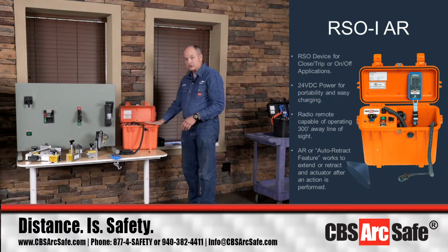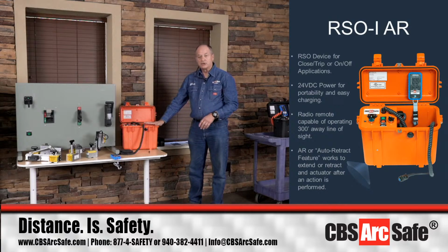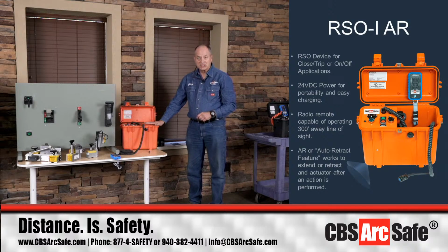It has a smart cycle charger in there, but you're not going to have enough power coming off the charger to operate an actuator and have the ampacity to move that big motor on a big actuator. So don't try to operate this if the batteries are not holding a charge.